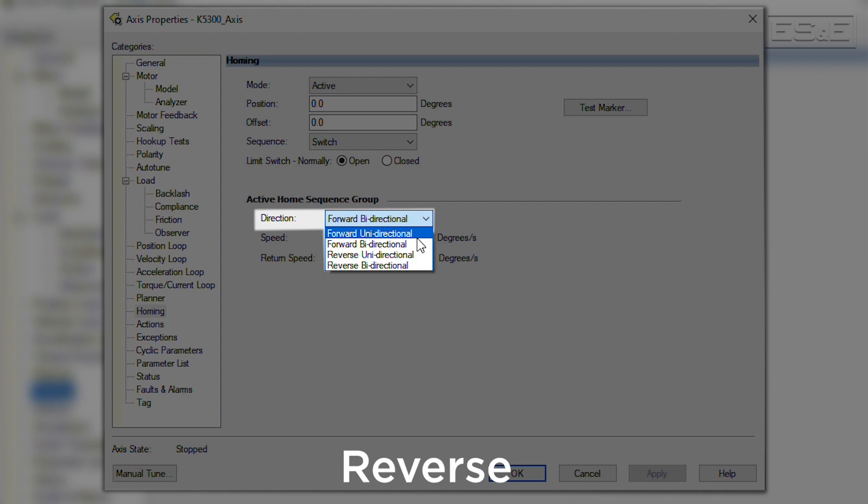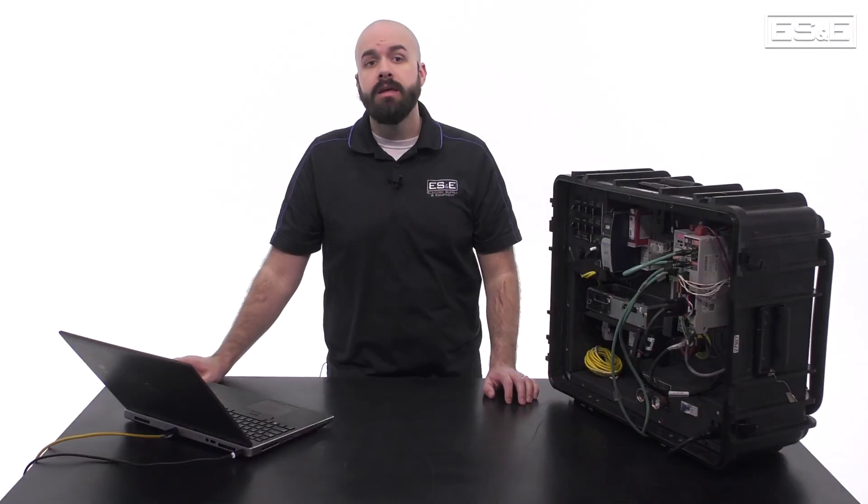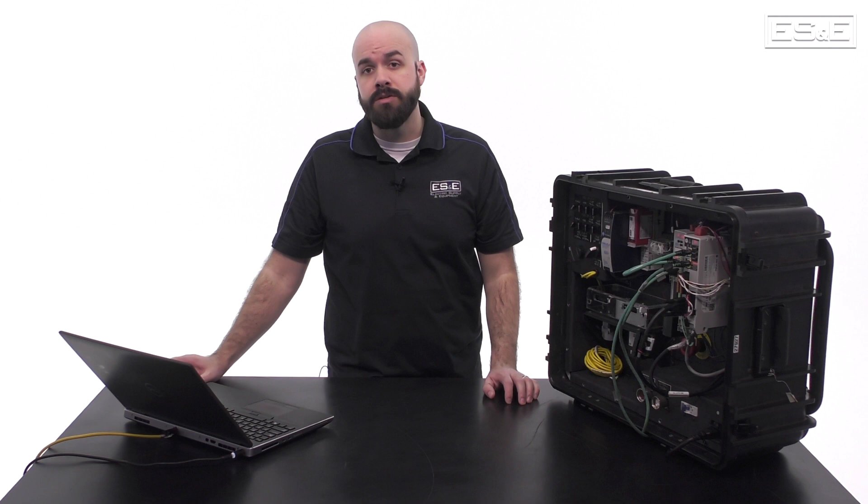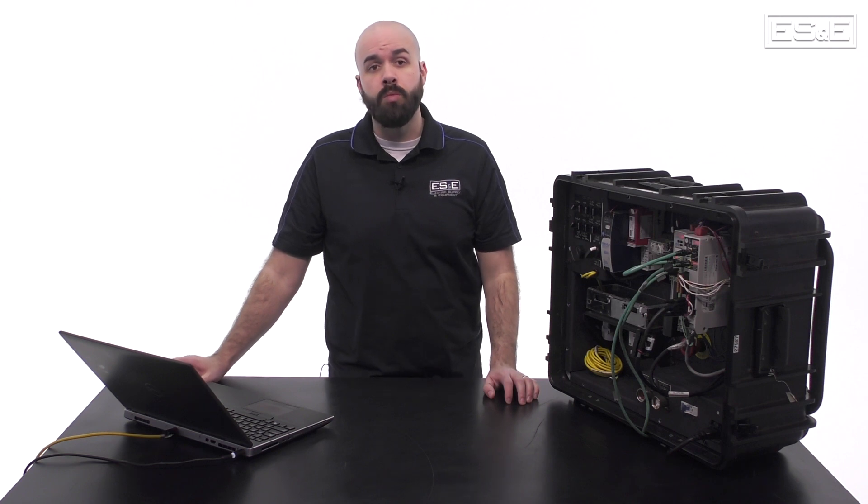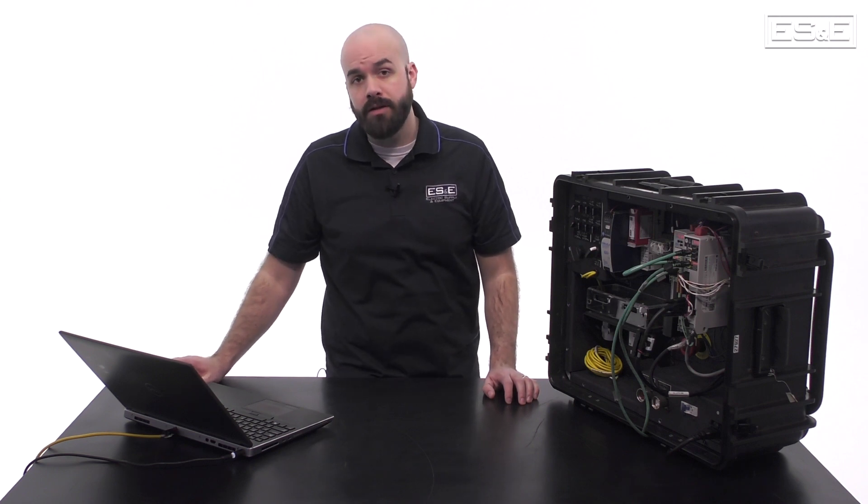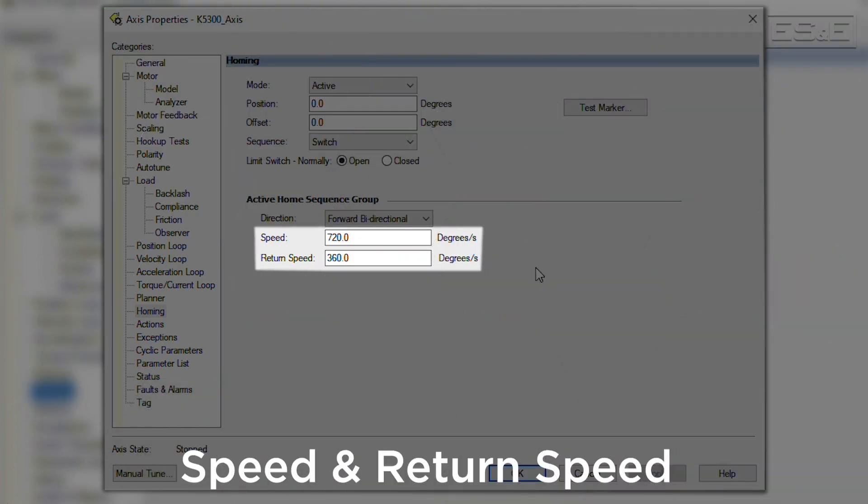Reverse moves the servo in the reverse direction. Unidirectional means that the servo will move to the home switch or marker pulse and then redefine the actual position when it is detected. Bidirectional means that the servo will move until the home switch or marker pulse is detected, and then it will reverse direction of motion until the home switch or marker pulse is no longer detected. This type of homing helps reduce the amount of error associated with using electromechanical and electromagnetic sensors. The speed field simply defines the speed at which the servo will move at each stage of the homing routine.